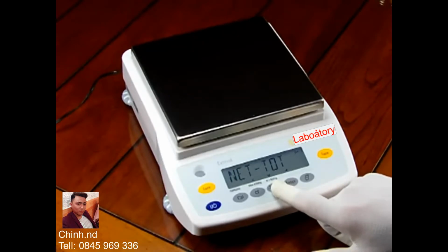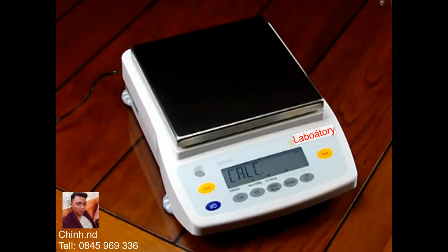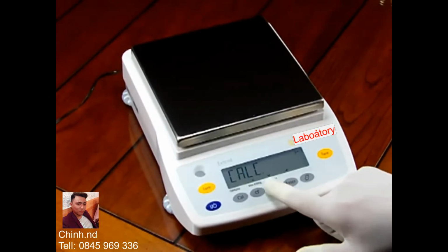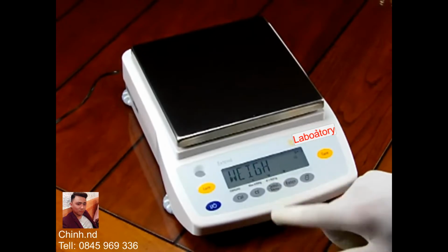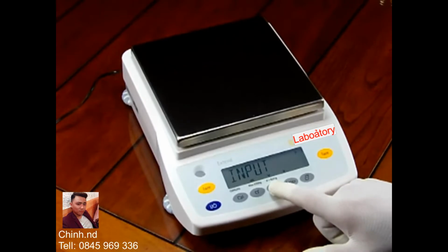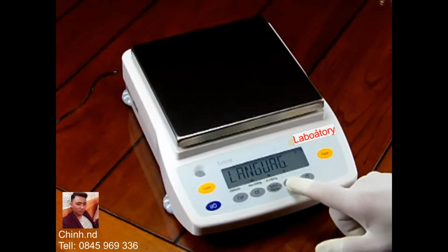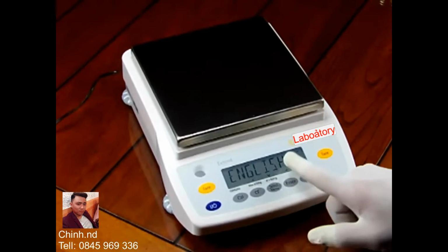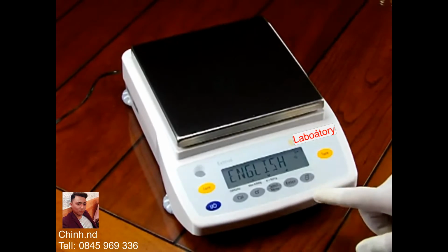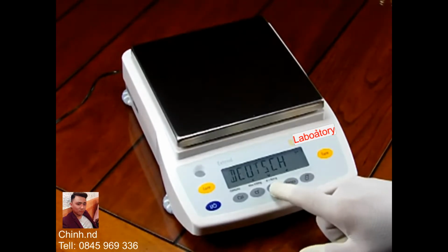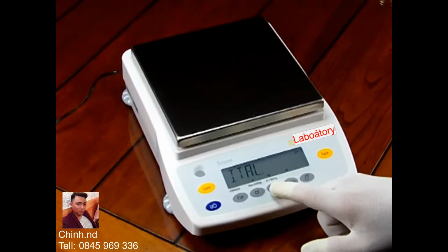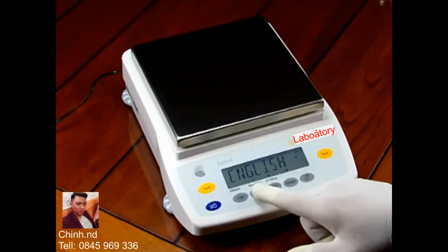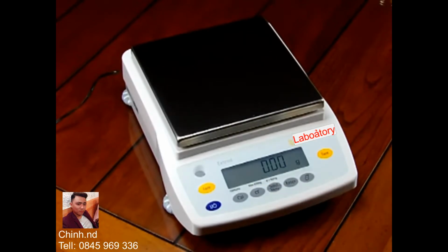The balance also offers net totalization, total, animal weigh mode, and you have a special feature where you can make your own weigh unit. So that's what this feature is. Then you also have density, and it brings you right back to the weigh mode. There's so many features with this balance. Here's where you can change the language. So if we go into the language mode, you can see English, and where this circle is in the top right hand corner, this is telling us that's what the mode is set to. But if we wanted to change it, we can change it to German, again French, Italian, Spanish, Polish. So the balance has a lot of features. To get out of it, we just hit the clear arrow.